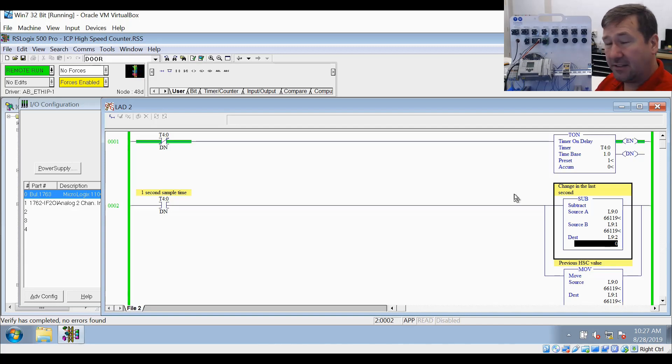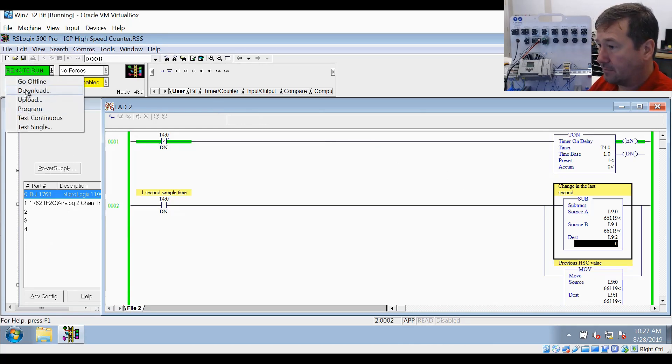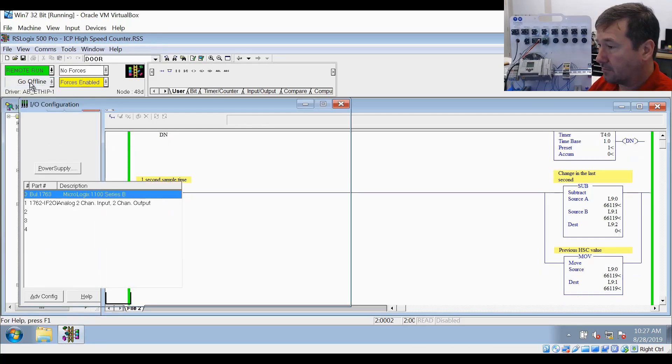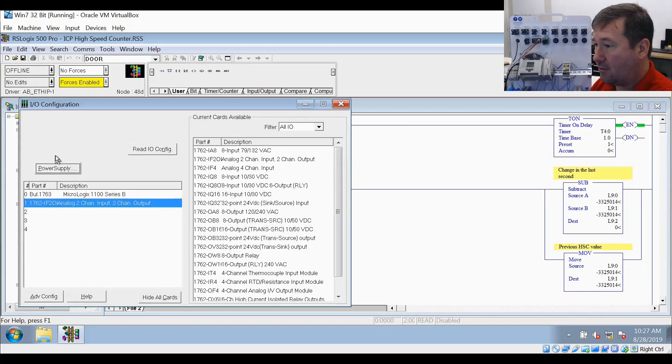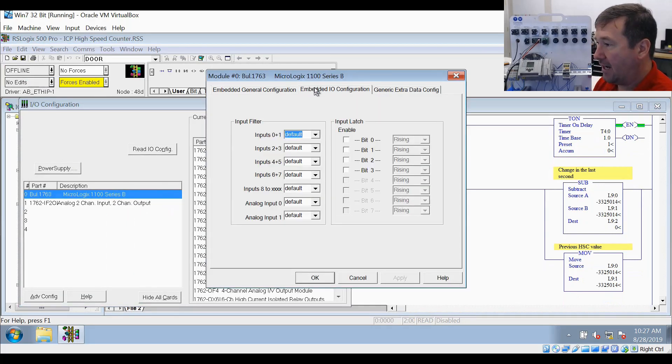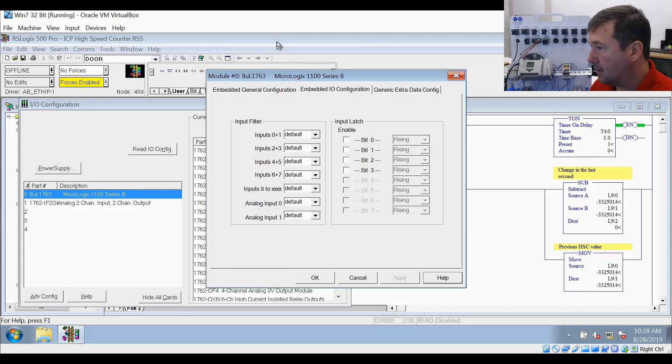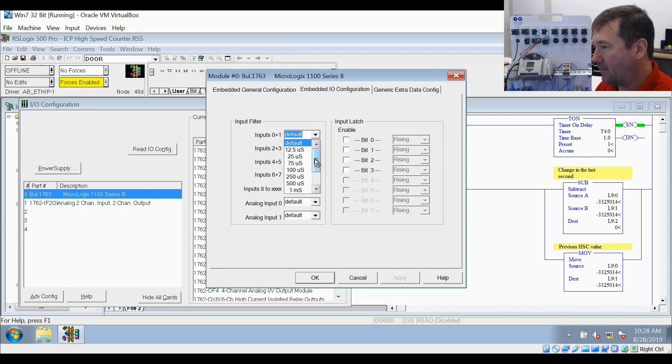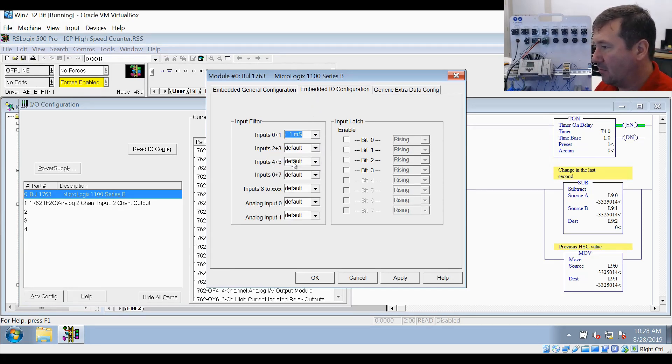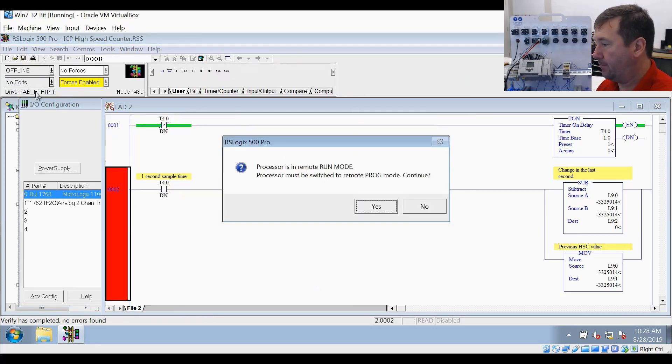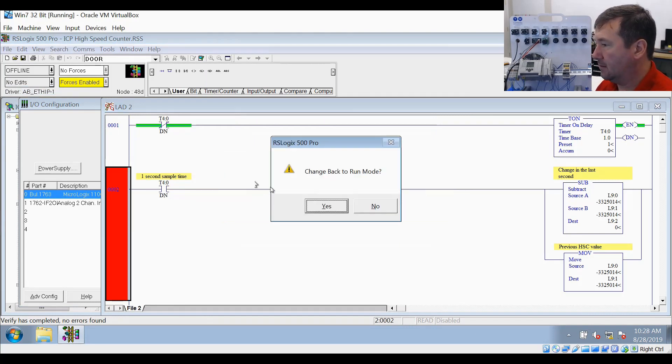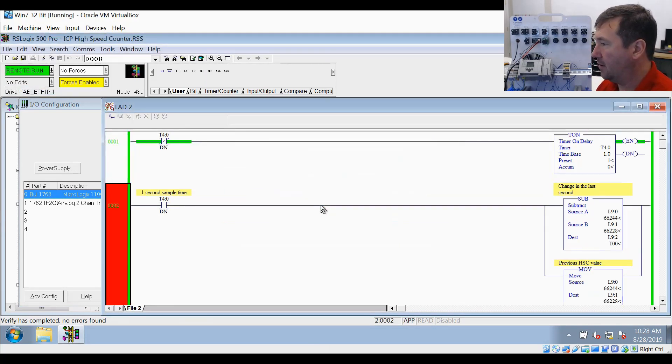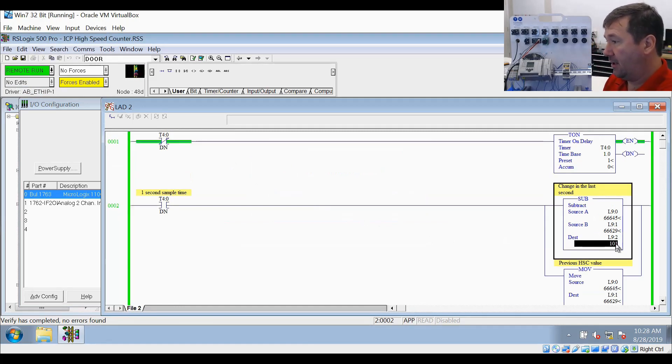Now let's play with this a little bit. Let's go back offline and back to our I/O configuration, slot zero in the embedded I/O configuration. I believe the default is actually eight milliseconds - I couldn't find that for sure. But let's put it at one millisecond. We'll download that program and go back to run mode. And now we are showing 100 hertz, just as we should.